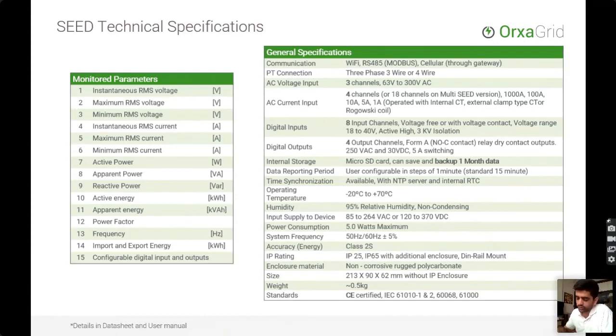We sample per phase voltage and currents at about 1.6 kilohertz, and we recreate the entire waveform. Through the high speed sampling and recreating the waveform, we are in a position to also do power quality measurements if required, as well as energy calculations, import energy, export energy, the four quadrant method, and the device is also capable of acting as a backup or a check meter for accumulated energy. This way it can support billing purposes as well with a 0.2 class accuracy on the device.